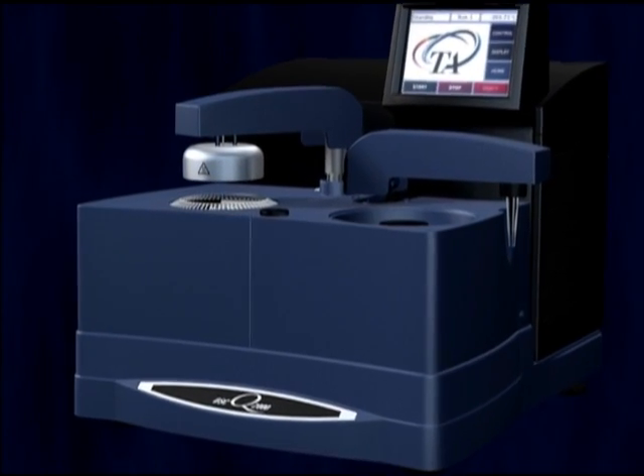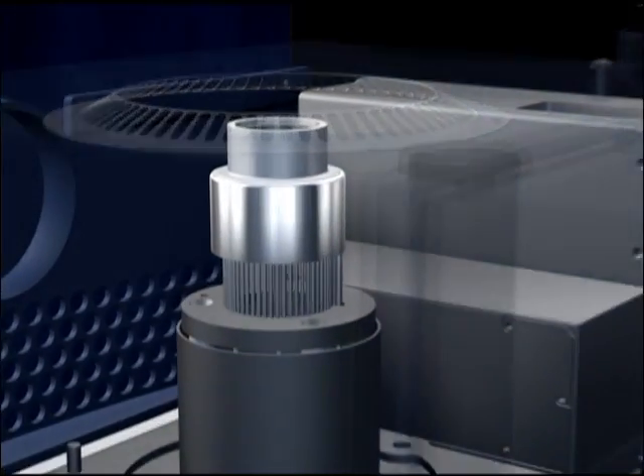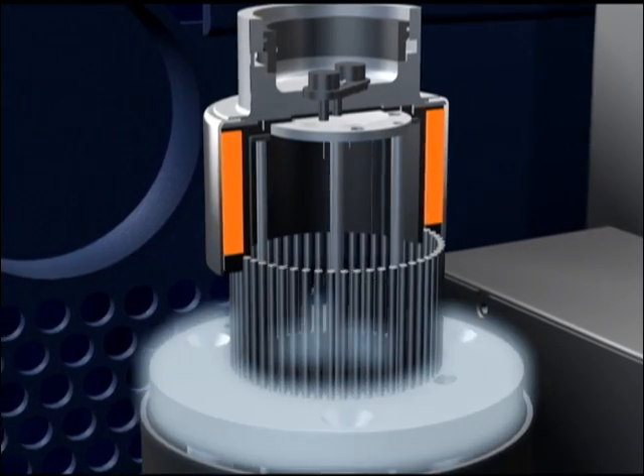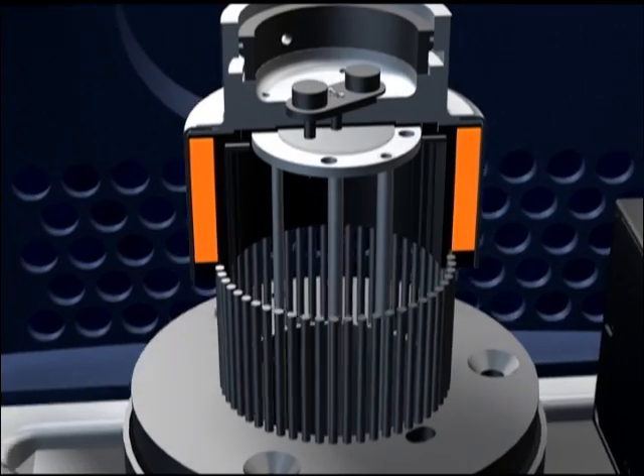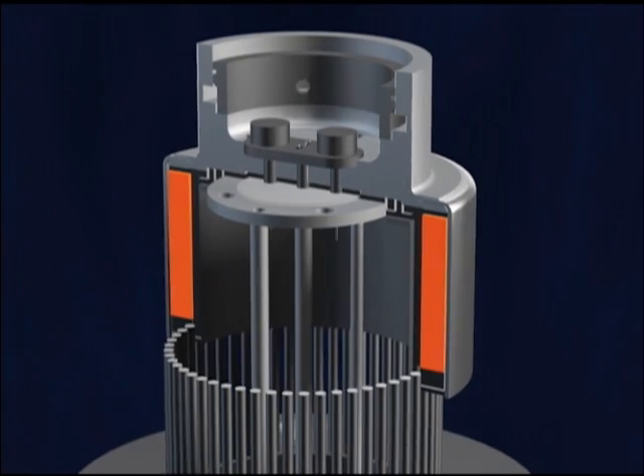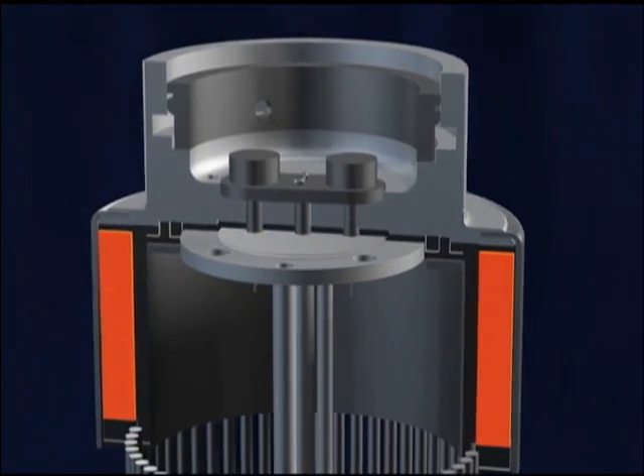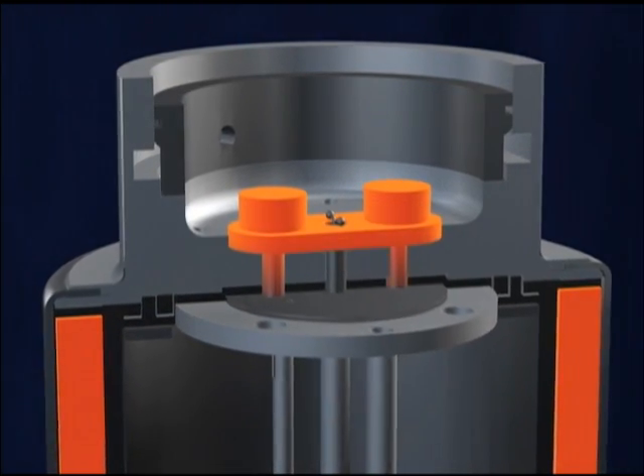The foundation of the Q-Series DSC is TA's proprietary T-Zero cell. This unique design incorporates a silver block furnace, a cooling flange, and 54 nickel rods to provide unparalleled temperature control. By incorporating key measurements not possible in competitive units, the T-Zero sensor supplies the most fundamentally accurate measurement of heat flow.